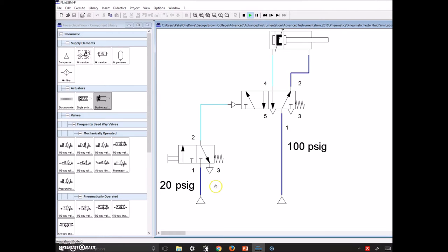The blue is our pressure — we have 20 psi here and when we press this button that's going to come over and toggle this 5/2 into the other position. At rest, the spring is denoting that this box is our rest state. This is a 3/2 — two positions to the valve, and three ports: one, two, and three. The 5/2 is going to have five ports and two positions. Similar to the 3/2, number one is the supply, number two is an output, and number three is the exhaust.